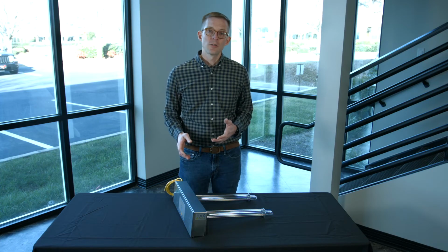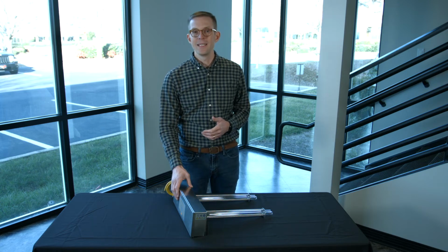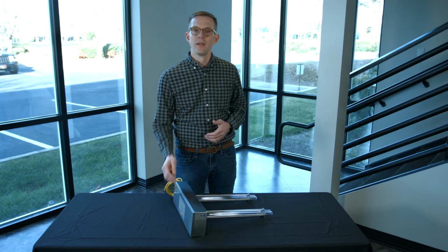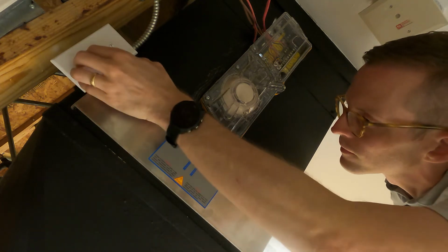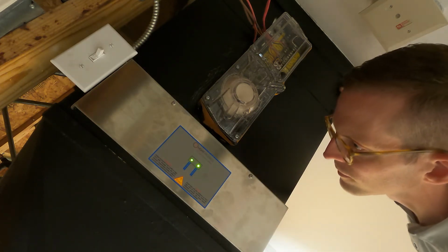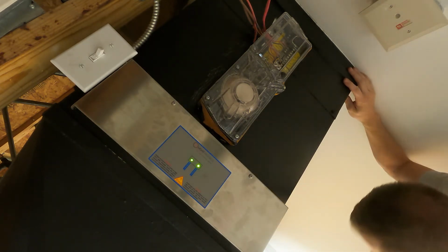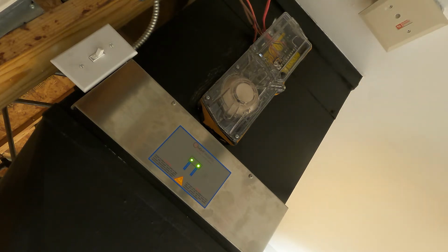The UV duct fixture also incorporates a couple of LED indicators on the front of the unit. Now, these are green as long as the lamps are operational, and these are a great indication without having to open up the unit of whether or not any maintenance is required on the UV duct unit, like replacing one of the lamps over time.